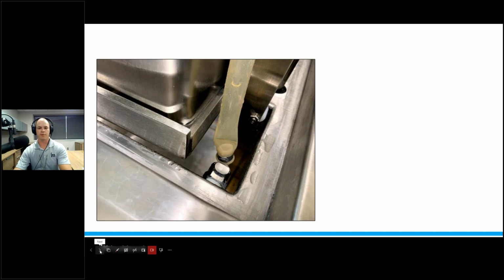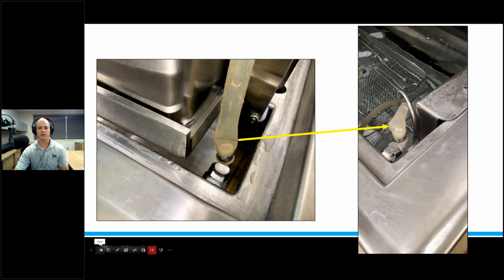Here's another example. This is a lumen flushing port that is like the other one that I showed you earlier in the first case study, where the tubing just isn't plugged in all the way. It probably is really tight and really hard to push in, because after time and wear and tear, these things do get really difficult sometimes to push in and snap into place. And what happened was, while the thing was running, water is shooting out everywhere, and the water pressure is diminishing inside that lumen cleaning circuit, if you will. So that is another potential problem here.